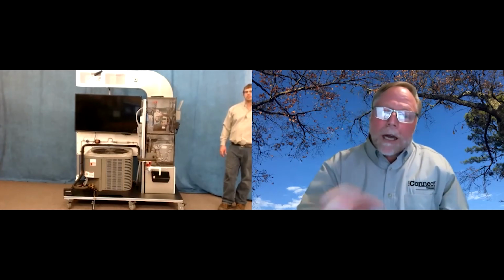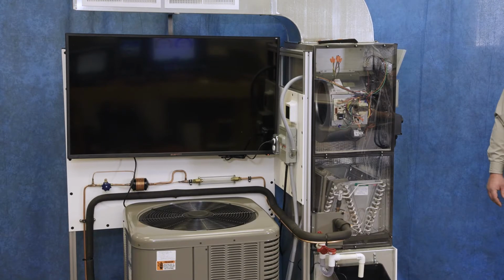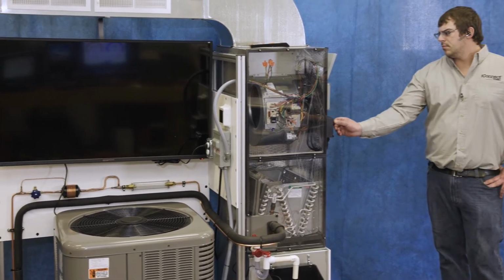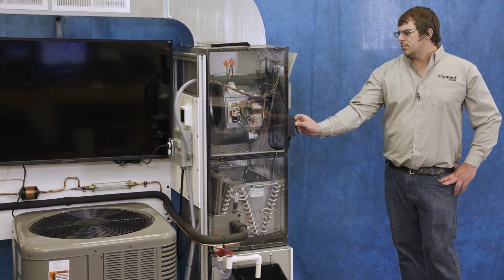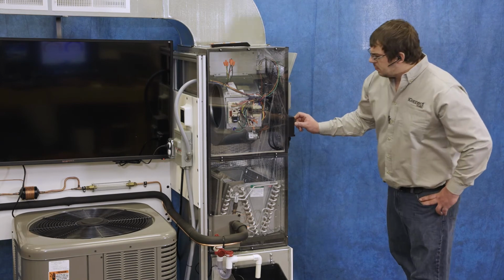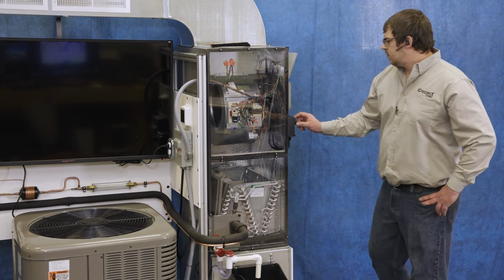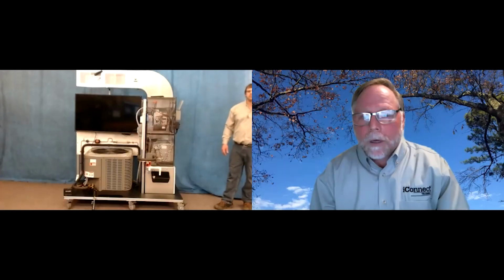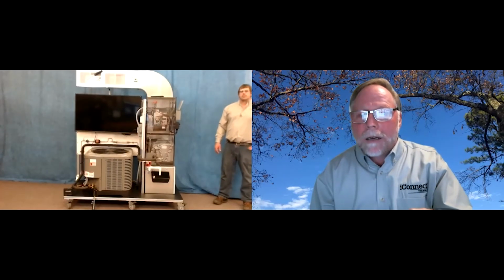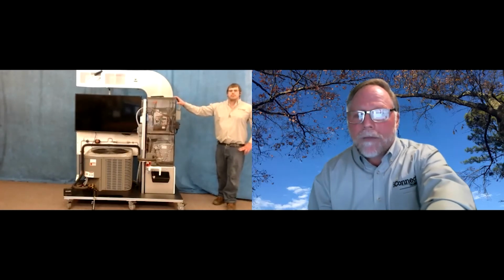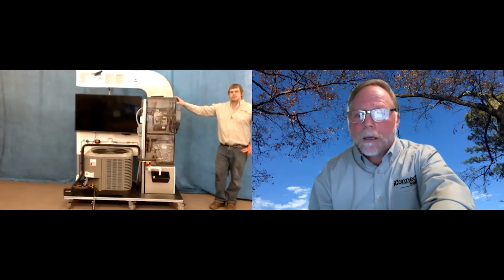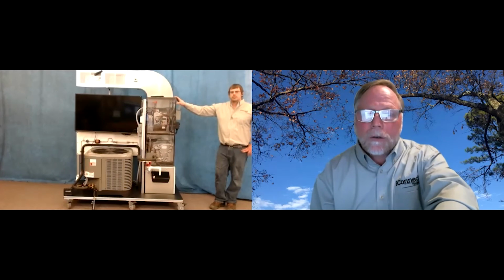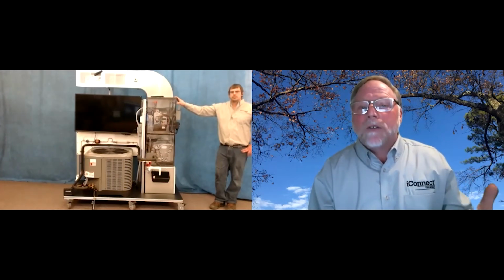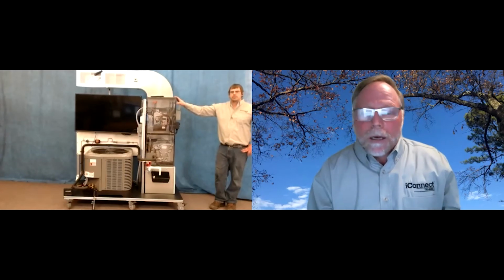Now, Nick, go ahead and turn the fan down even further. Let's let that filter get even dirtier. And there we go. We're getting down to 109, 108. Look at the evaporator temperature, down to 33, 32. Once it gets below 32, whatever condensation's in the air will eventually begin to freeze up on the coil.